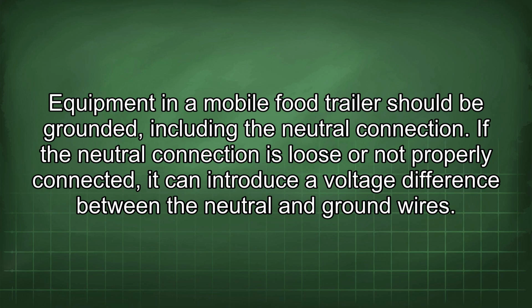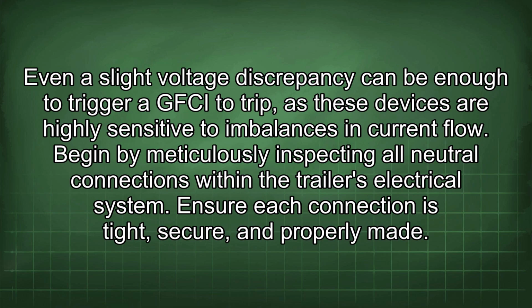If the neutral connection is loose or not properly connected, it can introduce a voltage difference between the neutral and ground wires. Even a slight voltage discrepancy can be enough to trigger a GFCI to trip, as these devices are highly sensitive to imbalances in current flow.